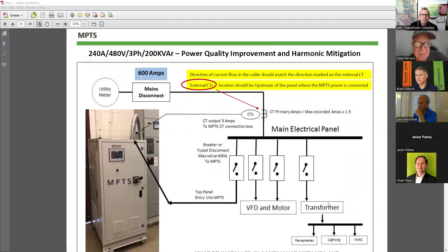So here is your schematic showing this switch - this MCCB - which is often available in the switchgear, like you have at that church site. You have a 400 amp MCCB or disconnect as part of the switchgear, so you don't need a separate disconnect switch - you simply tap here and take it to the MPTS. And this is the termination box for your CT wires to come in.